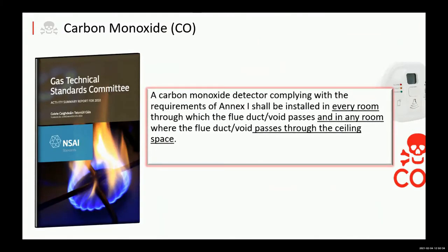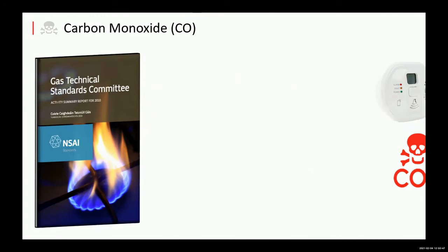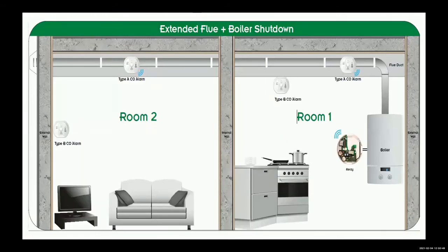Okay, so the carbon monoxide detector complying with the requirements of Annex I shall be installed in every room to which the flue or duct passes, and in any room where the duct or flue passes through the ceiling space. So if we look at this graphic, we see the boiler on the right-hand side. You have an extension of the boiler up on a vertical flue, goes into an elbow, and then it goes horizontally across two rooms and out onto an external wall.